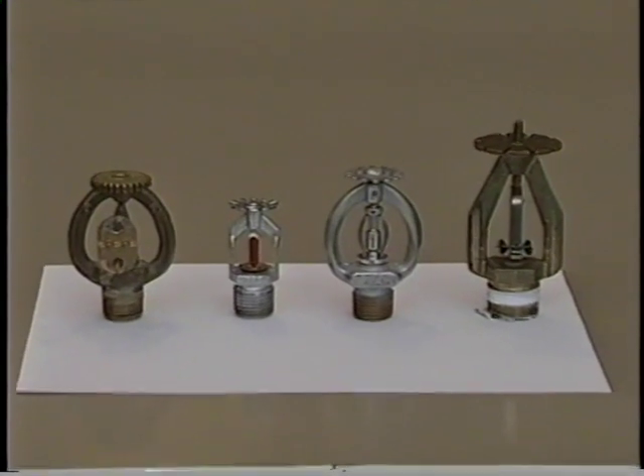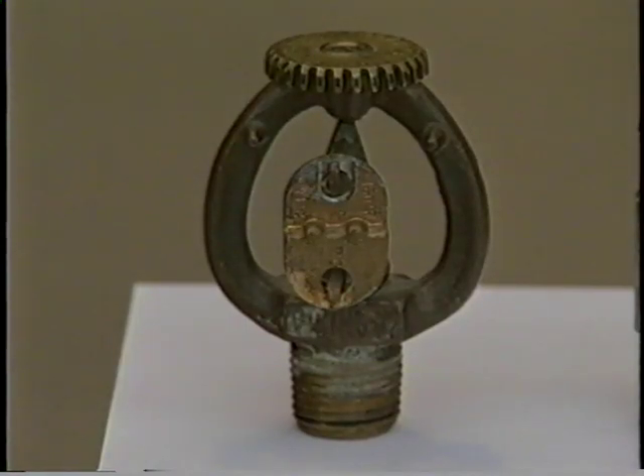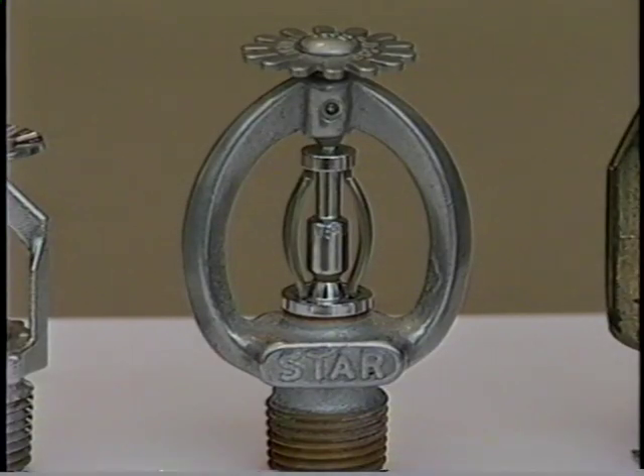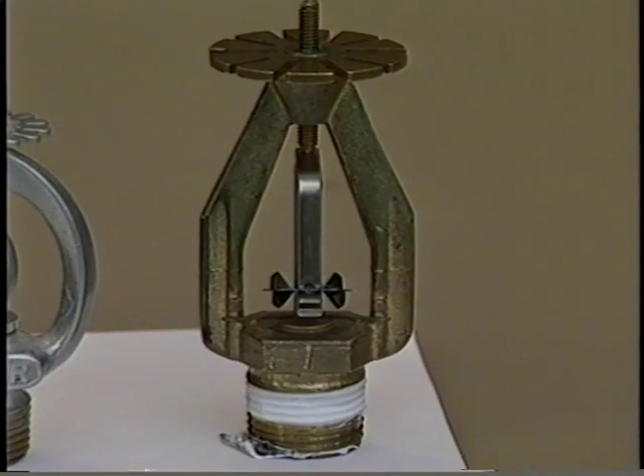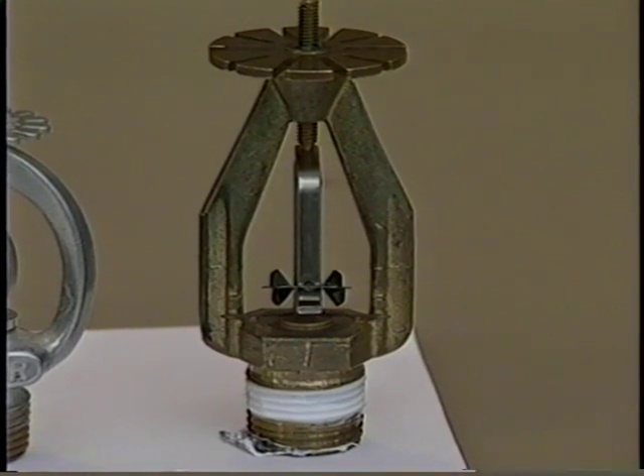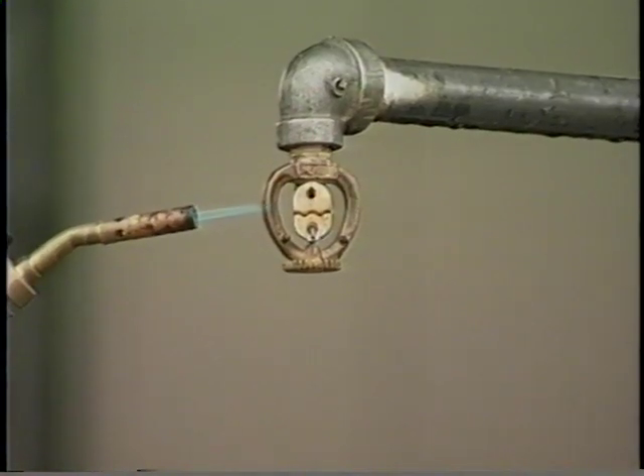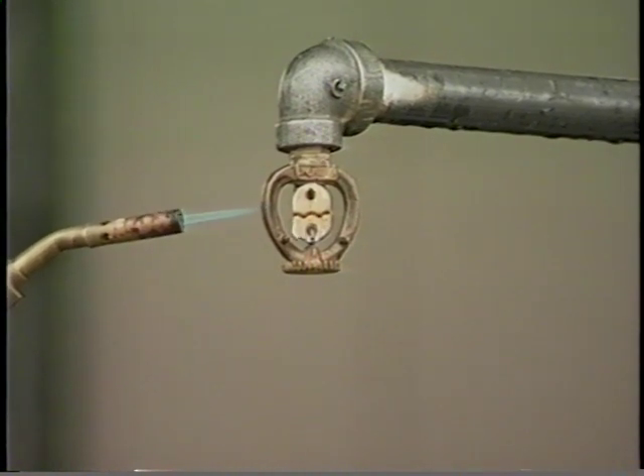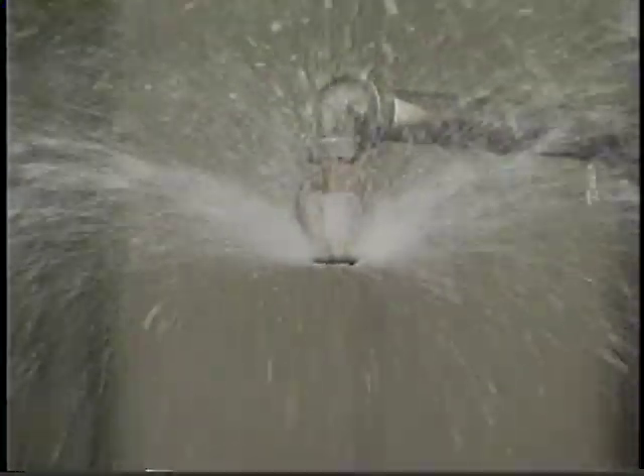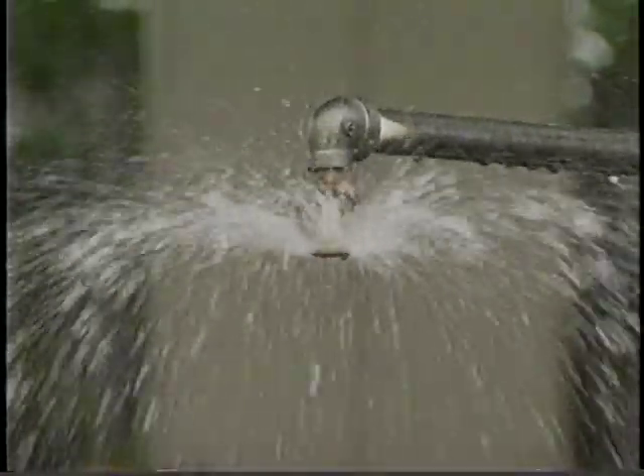Four of the most commonly used release mechanisms are fusible links, glass bulbs, chemical pellets, and quick response mechanisms that fuse or open in response to heat. In a fusible link sprinkler, the water is held back by two levers pressing against a cap over the sprinkler opening. A fusible link holds the levers together until the link is melted during a fire. Then the water pushes the levers and the cap out of the way and strikes the deflector on the end of the frame. The deflector converts the standard half-inch water stream into a wider spray.